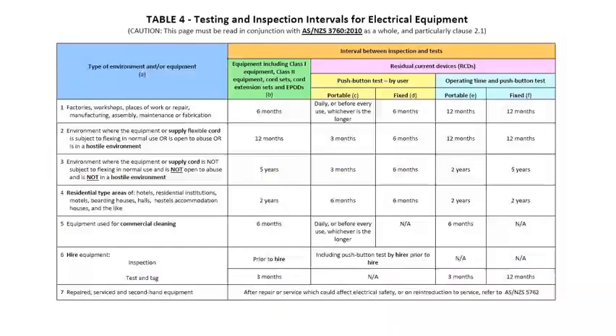As a professional test and tag company, we recommend that companies follow the AS/NZS 3760 standard. This table shows the intervals at which electrical equipment should be tested. It does get a little confusing, but I'll break it down for you. So if you're in construction, building commercial properties, residential properties, or a trade associated with helping those trades, like plumbers, electricians and the like, then your equipment should be tested every 3 months.